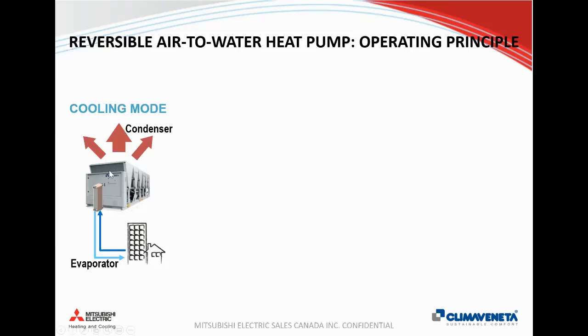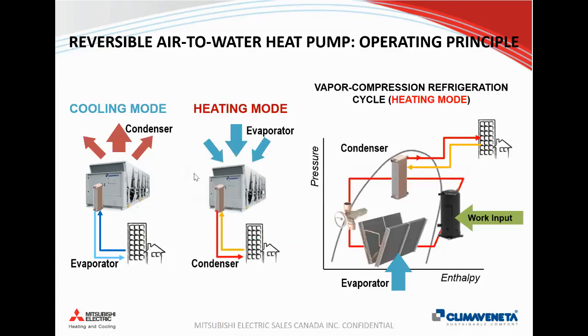And that means that we're basically using the integrated coil on the machine as a heat sink, and we're rejecting heat to the atmosphere. So any heat that we don't want in our building through the chilled water circuit, we're rejecting that outside. Simply put, the air-to-water heat pump is essentially an air-cooled chiller that is run in reverse.